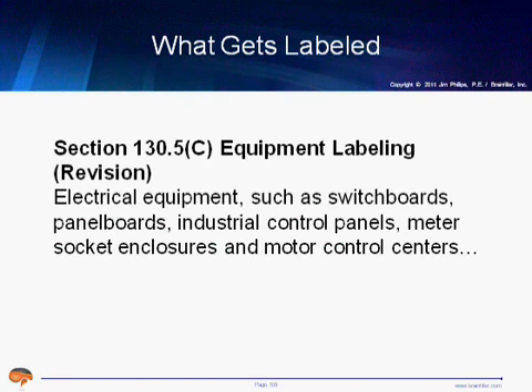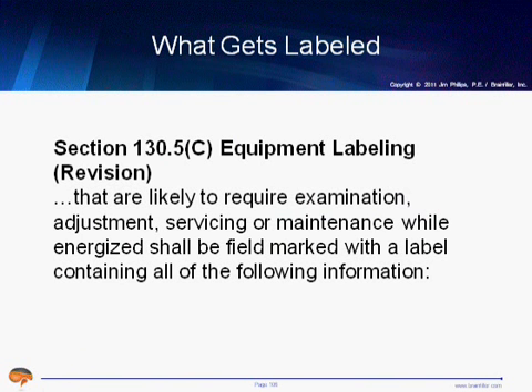And it's electrical equipment such as switchboards, panel boards, industrial control panels, very similar to what you find in the National Electrical Code. It's not inclusive. It says equipment such as. And the other part of this is it's equipment that's likely to require examination, adjustment, servicing, or maintenance. So they're being more specific about the equipment that is to be labeled.